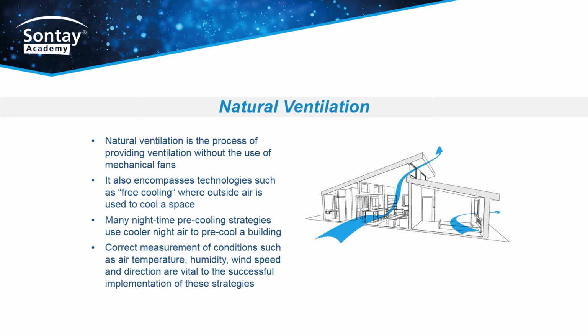Natural ventilation. Natural ventilation is the process of providing ventilation without the use of mechanical fans. It also encompasses technologies such as free cooling, where outside air is used to cool a space. Many nighttime pre-cooling strategies use cooler night air to pre-cool a building. Correct measurement of conditions such as air temperature, humidity, and wind speed and direction are vital to the successful implementation of these strategies.